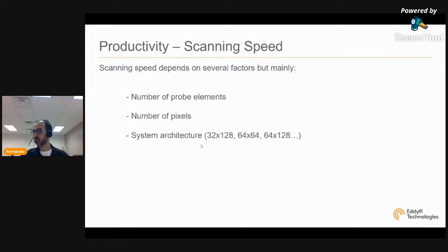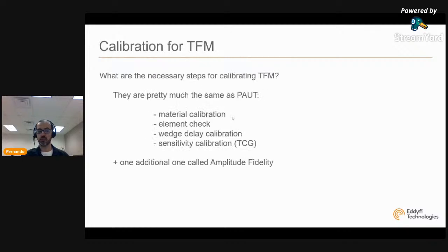One of the things FMC gets downgraded on is the speed. But there are things you can do to increase the speed depending on the unit: the number of elements in the probe, the number of pixels, and the system architecture. So you have 32:128, 64:64, 64:128. All those parameters are going to affect the scanning speed. The calibration process is pretty much the same. You still have the element check and wedge delay sensitivity. There's another one called amplitude fidelity.